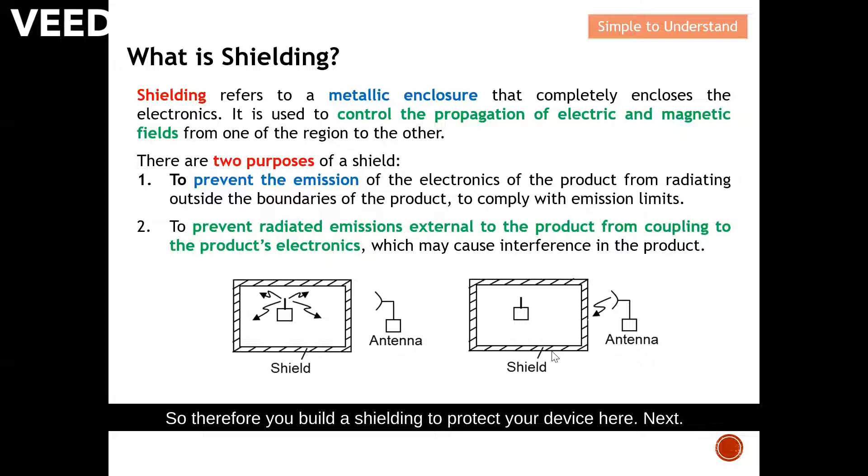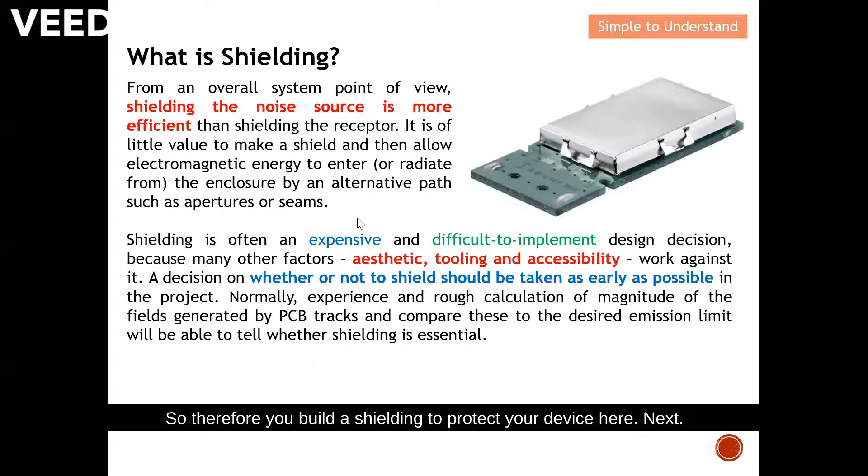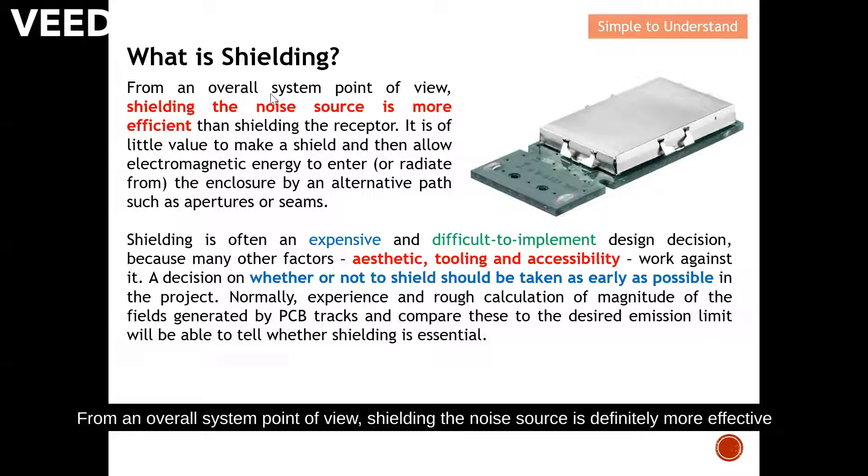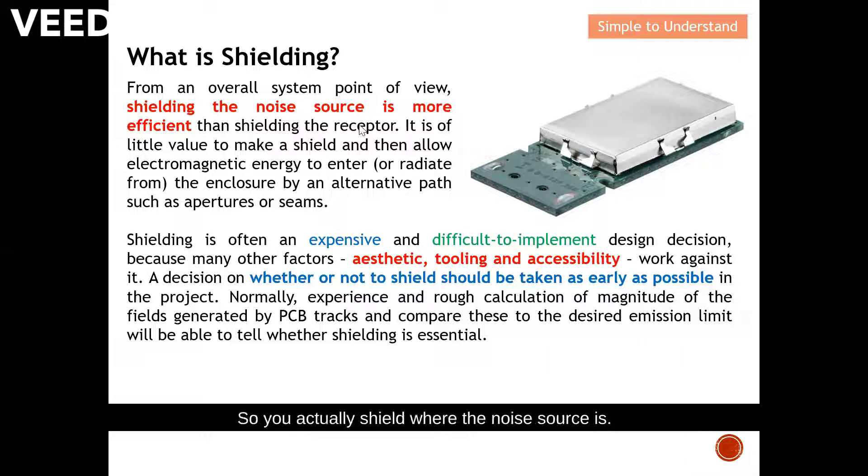From an overall system point of view, shielding the noise source is more efficient than shielding the receiver. If you know where the noise source is, shield that source. It is of very little value to make a shield and then allow electromagnetic energy to enter or leave the enclosure by an alternative path such as apertures or seams.